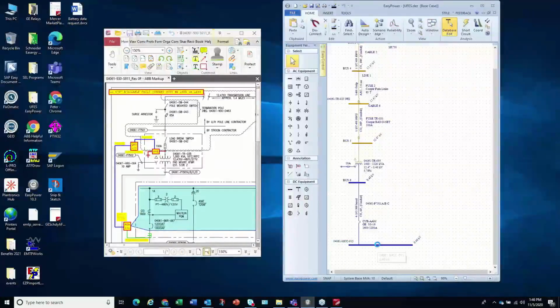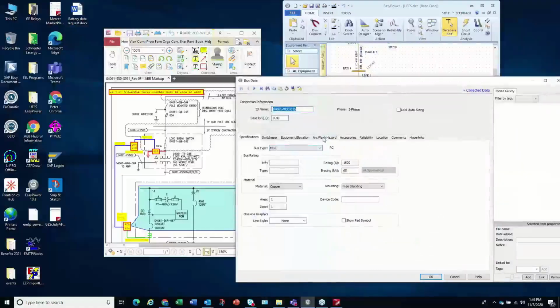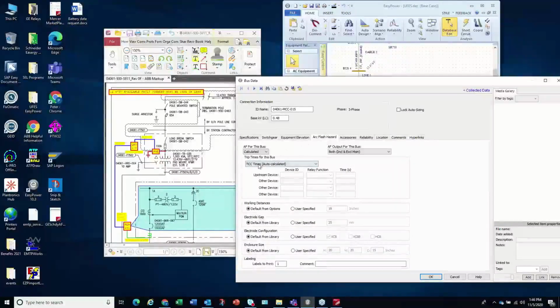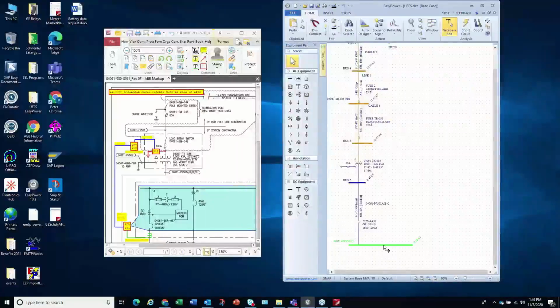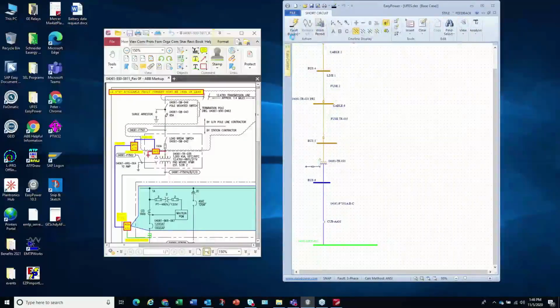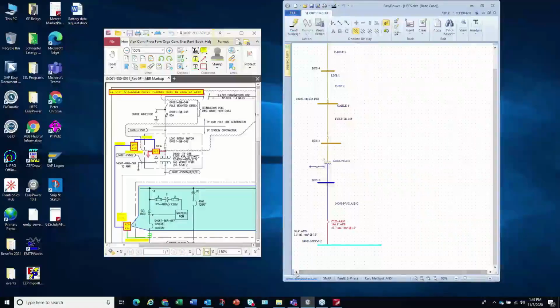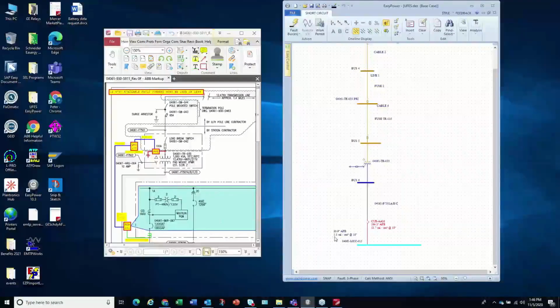So if we look at it now in the database model, what we have is just an automatically calculated time current curve, and we're going to look at both including and excluding main arc flash. So we go here, and what we see is on the bus itself, we get 1.5 calories. That's limited by the main breaker. And then on the line side of the main breaker here, we're going to get 53 calories, which is higher than you want to be exposed to, shall we say.